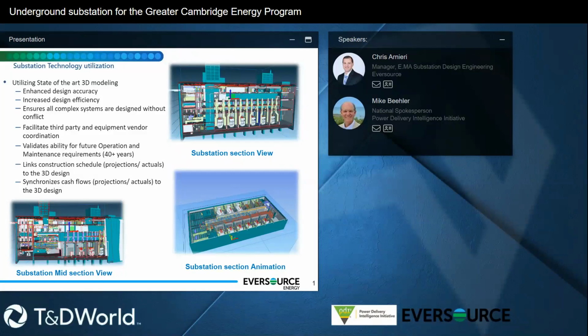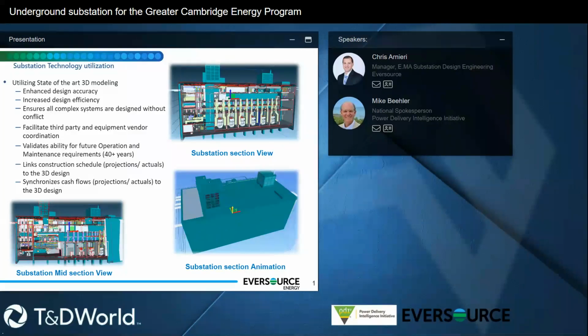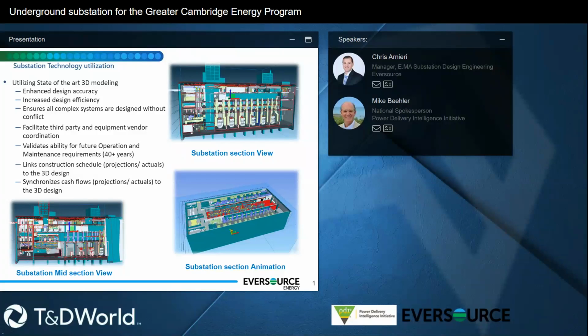That's what I'm trying to showcase here: the technology utilization. We were able to increase our design accuracy and efficiency because not only could we share our model with partners like BXP, but also with our manufacturers for the GIS, the transformers, the metal clad switchgear, our duct banks, our bus ducts, and things like that. Each group was able to add their pieces to the model, and we could clearly see a clash very quickly and work very smoothly.